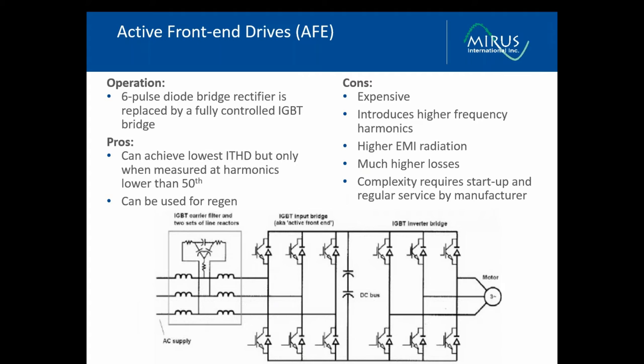We're also seeing a lot of applications of active front end drives. An active front end, an AFE system, takes the normal diode bridge rectifier on the input of the drive and uses an IGBT inverter bridge instead. And this can be switched with very high switching frequencies and in such a manner that it draws current that is more sinusoidal, particularly if we are looking at harmonics up to the 50th.